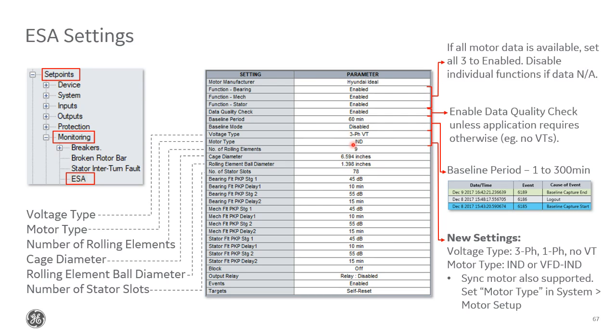And then we also added an option for the motor type. Again, we can support induction motors. If it's a simple induction motor, you would choose this option. If you have a VFD fed induction motor, you would choose VFD induction. And we also support synchronous motors, in which case you would leave this as is, but make sure in the actual motor setup settings that we saw in the last slide that you set up the motor type as synchronous motor. And then the ESA will take a look at it accordingly.